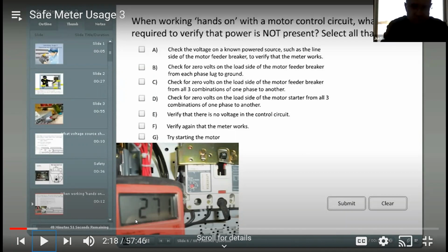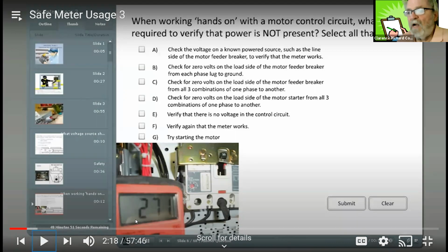Yeah. Okay, we're prepping our meter. We're making sure that when we go to a place where we're expecting no voltage, the meter is actually working right. Okay, how about B? Check for 0 volts. This is where that probe is at, on the load side of that circuit breaker. Check for 0 volts on the load side of that motor feeder breaker from each phase lug to ground.